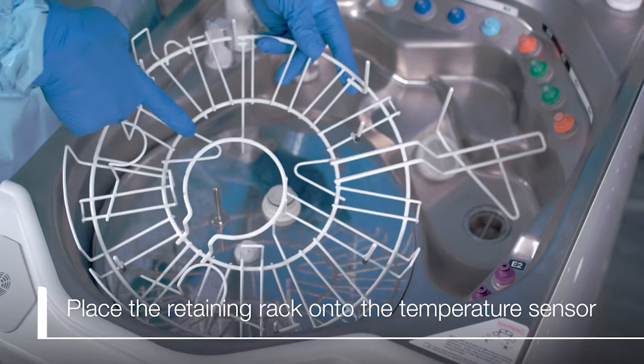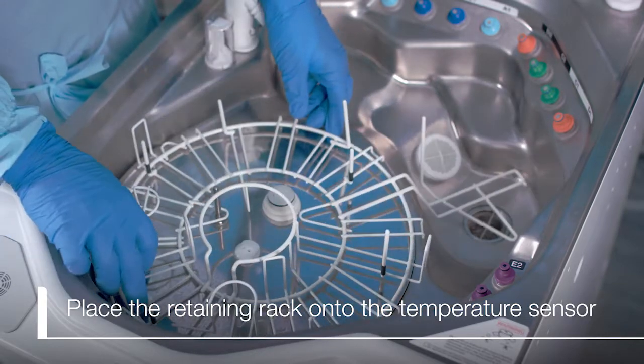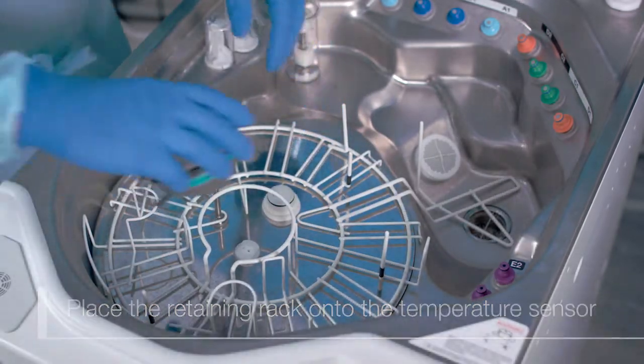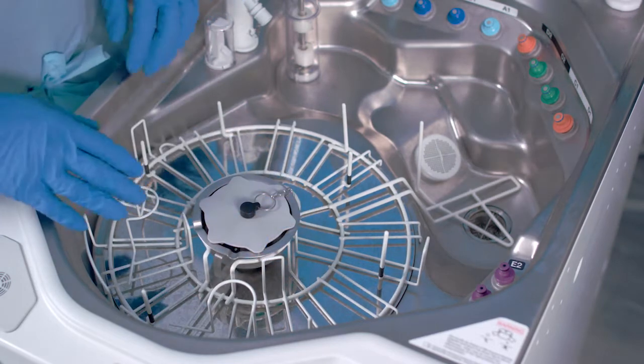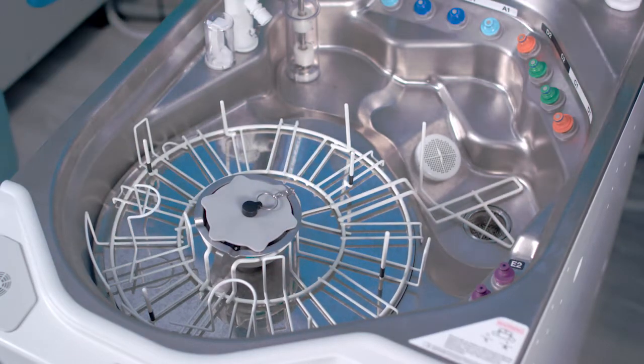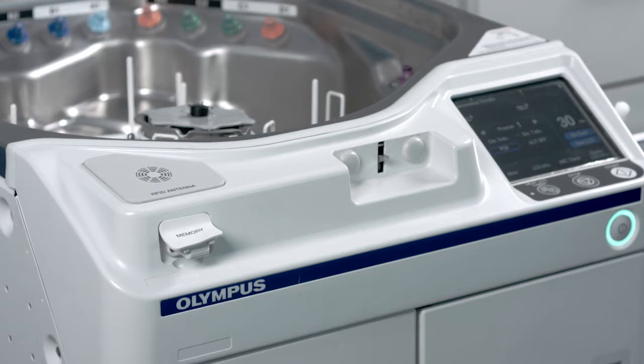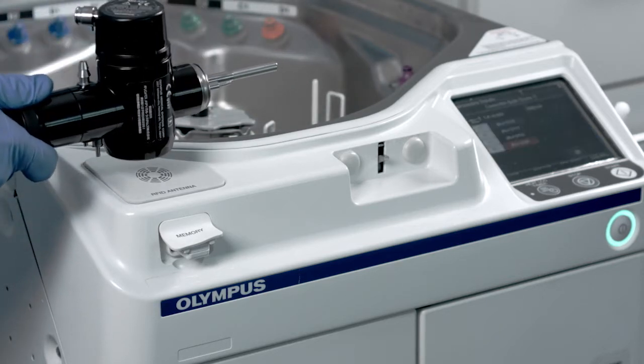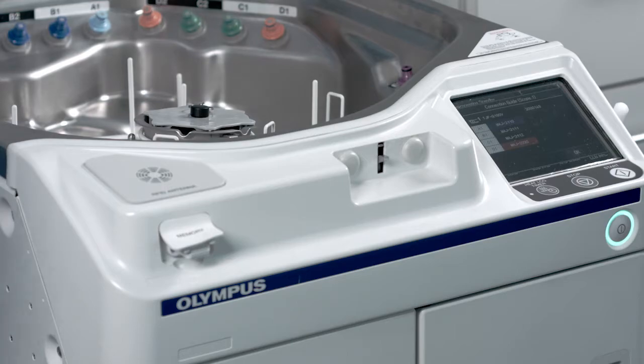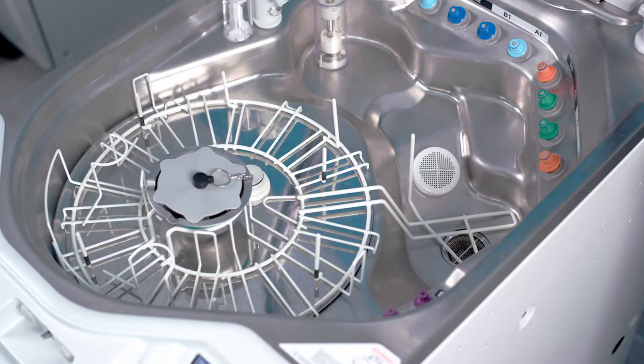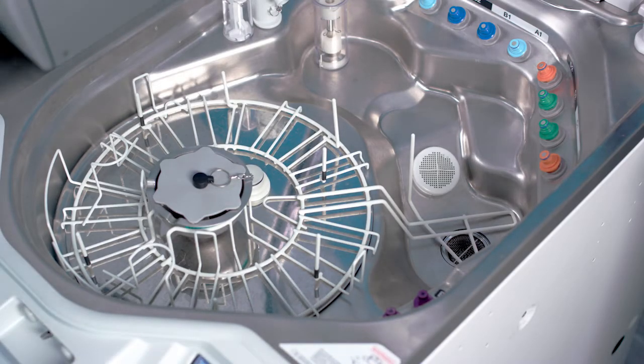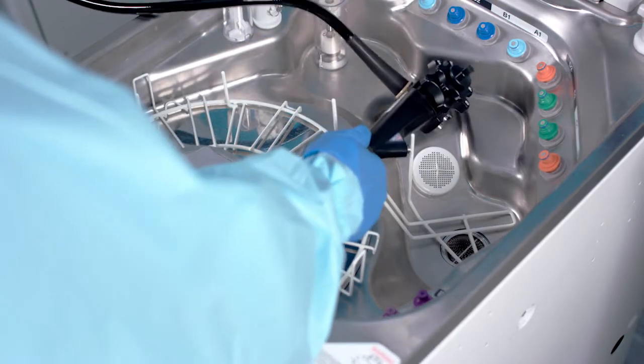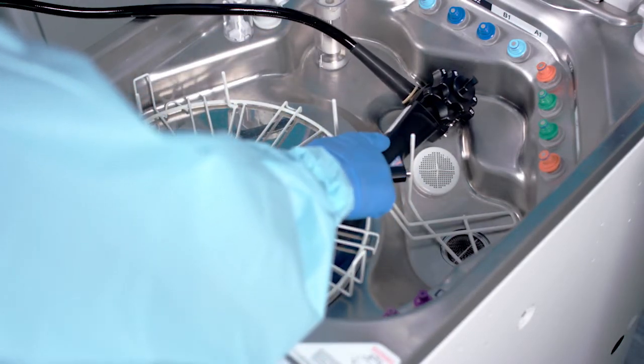Now, let's get started. First, fit the ring of the retaining rack onto the temperature sensor of the reprocessing basin. This ensures that it's seated properly inside of the OER-Elite basin. Now that the retaining rack is installed and the accessories are removed from the endoscope, let's begin the loading process. Scan the scope RFID tag over the OER-Elite RFID reader. Set the control section to the left of the index pin. This is located on the deepest part of the reprocessing basin.